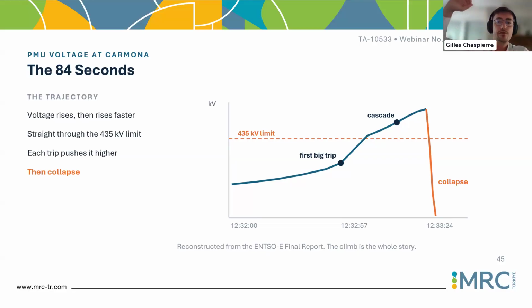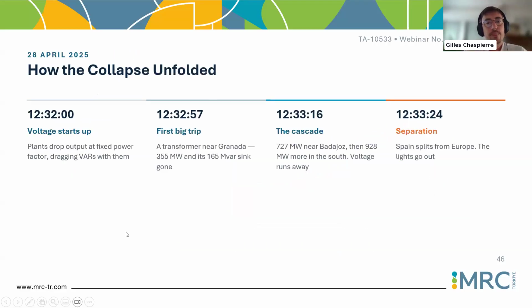The voltage is rising very, very fast until, of course, you reach a breaking point where all the units trip, you are separated from the rest of Europe, and your system goes black. It's a collapse. Yes, you can go to the next slide. Yeah, I think it's a bit what I have explained. What I think is important here to highlight is, again, you see between 12:32 and 12:33, 24 seconds is the complete separation. So in 84 seconds we go black. So I think again, quite scary. Hopefully the operational rules will be updated fast enough to make sure we will not face that event in the future.